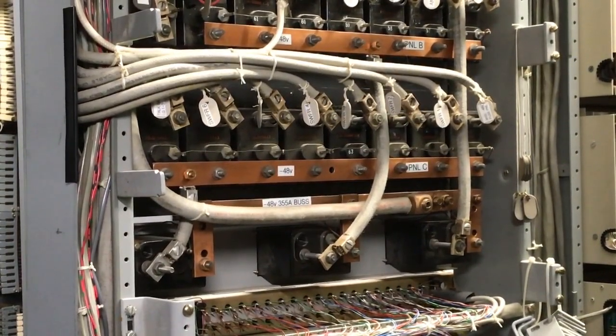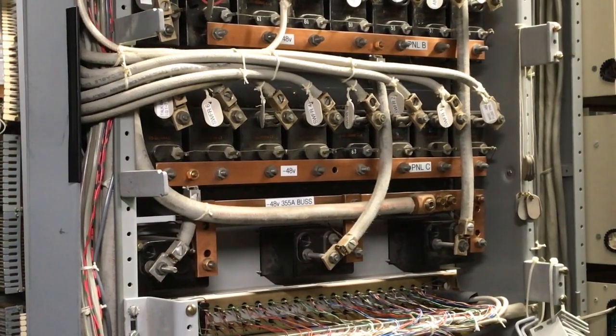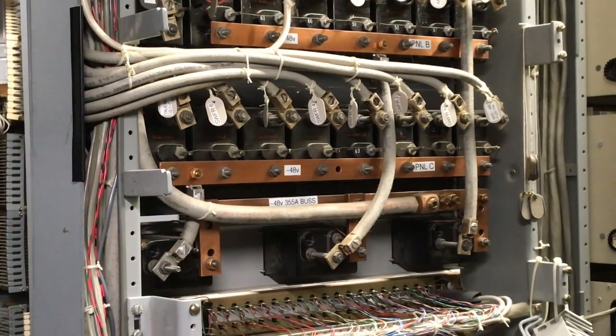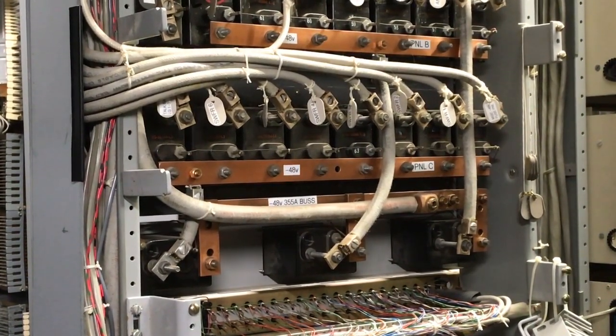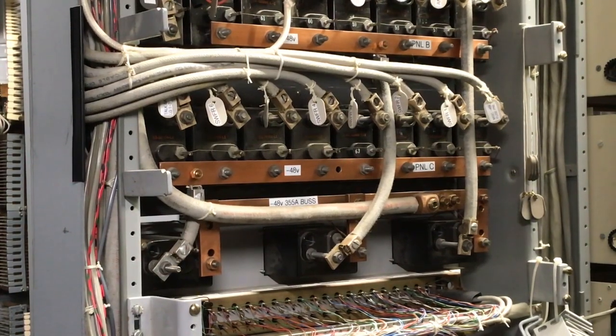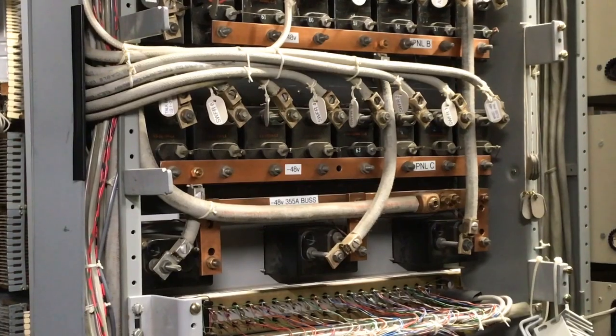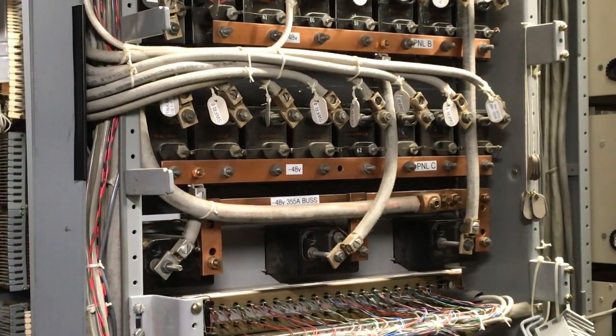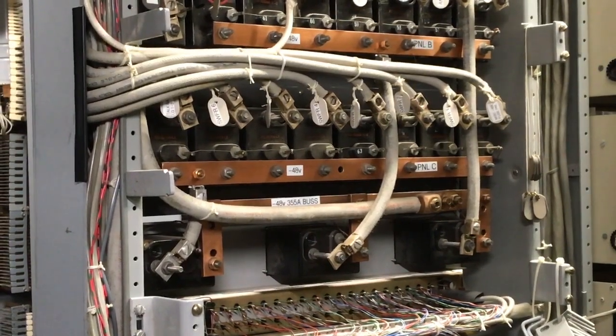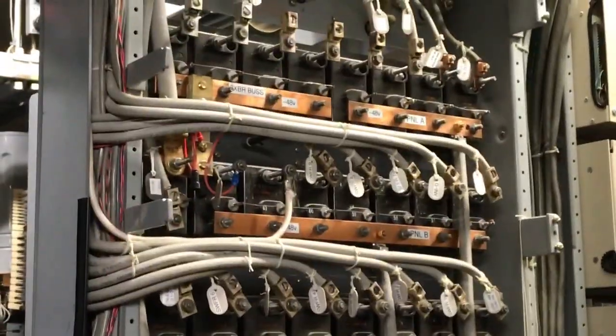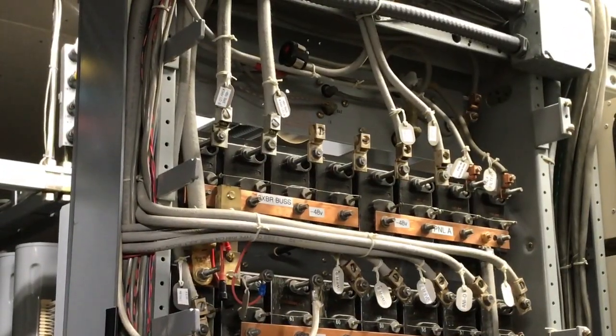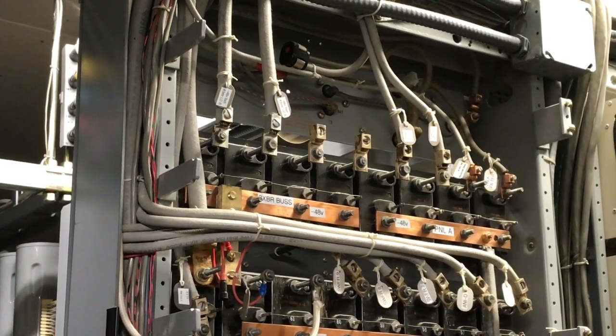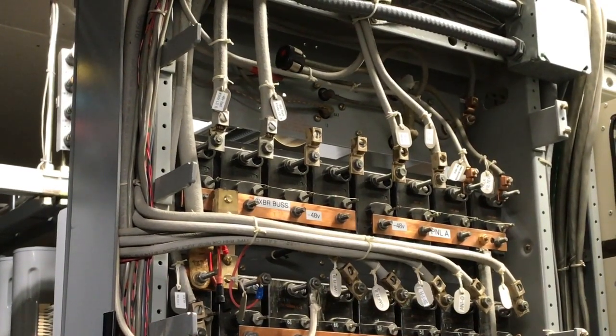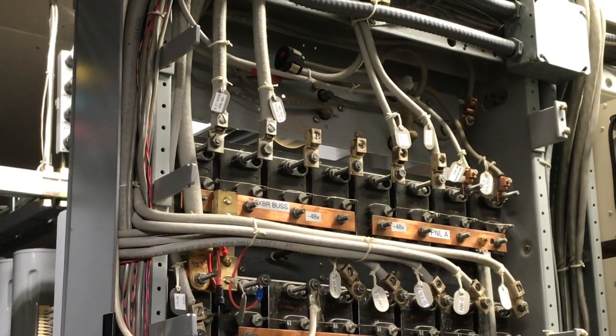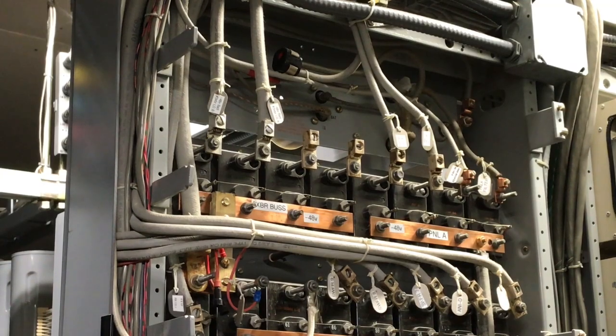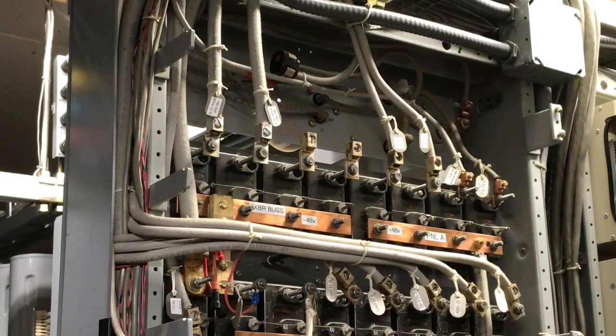I can individually remove the power from 8 circuits at one time by taking out the big fuses. The big fuses are set up for approximately 30 amp loads, I believe, and then the remaining circuits are 5 to 10, 15 amps, depending on what they're actually connected to. The very top fuse panel, the very left 2 conductors are feed to the number 3 crossbar, and then the other conductors are feed to filters and miscellaneous fuse panels.